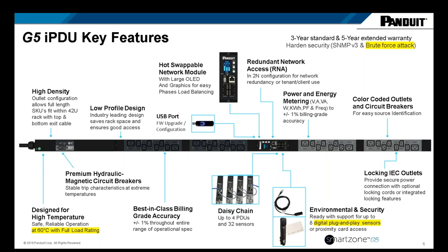What that means is when you plug a sensor into our PDU, the sensor has firmware and so does the PDU, and they talk to each other—the sensor tells it what kind of sensor it is. So if it's a water rope sensor, it tells the PDU it's a rope sensor, and you can immediately start setting your thresholds. If it's a temperature sensor, it tells it that too. You don't have to go in and define what it is because it already knows.